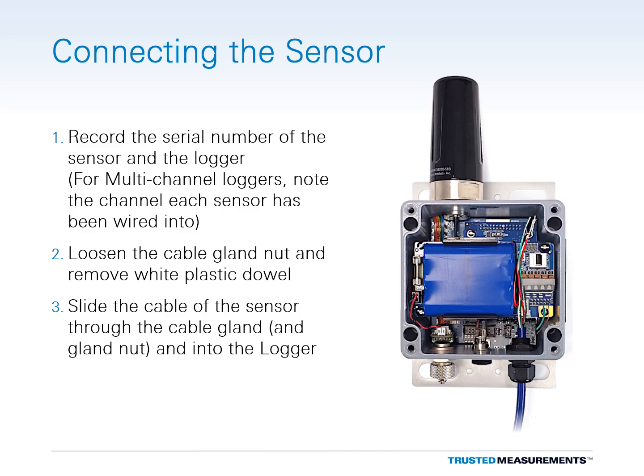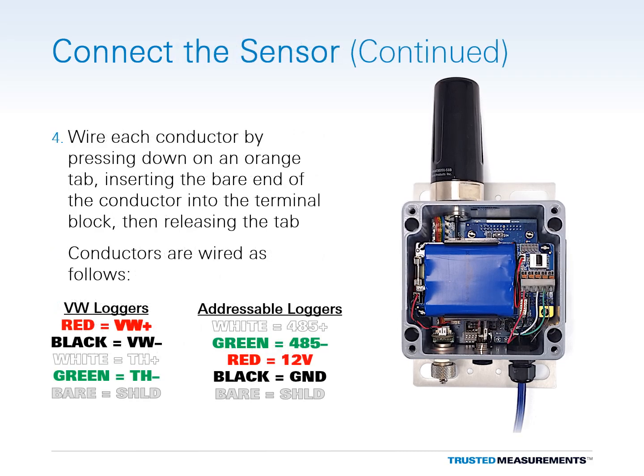To connect the sensor, loosen the cable gland nut and remove the white plastic dowel. Slide the cable through the cable gland and the cable gland nut and into the interior of the logger. Wire each conductor of the cable into the terminal block by pressing down on an orange tab, inserting the bare end of the conductor, and then releasing the orange tab. Cable conductors are wired as shown.